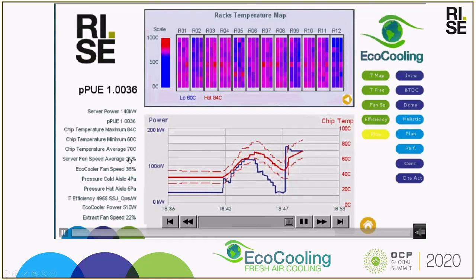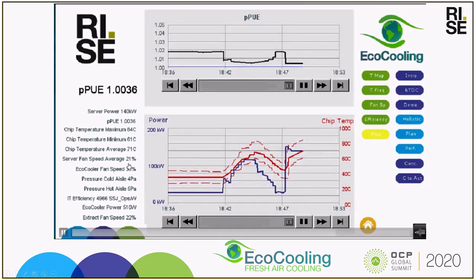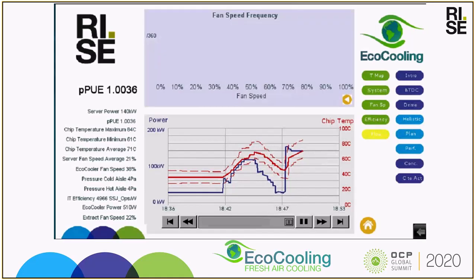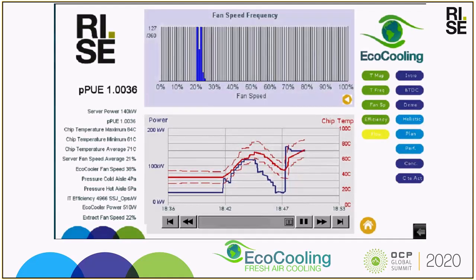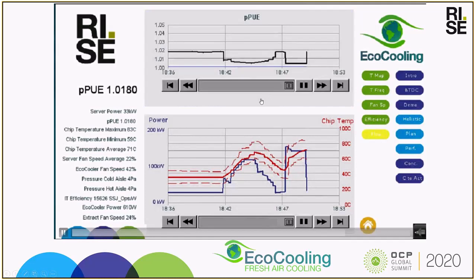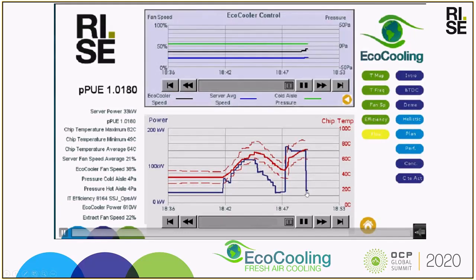With a little bit of a speed up, because now the microprocessor temperatures are a little bit hot, the servers are saying now I need a bit more air to cool these down. Now 22% is the average server fan speed here, you can see, and the histogram is moving towards the right rapidly. The workload has jumped off the data center now. You can see that we've just rapidly jumped back down to idle power, slightly more than the normal 28 kilowatts as the fans start to slow down.